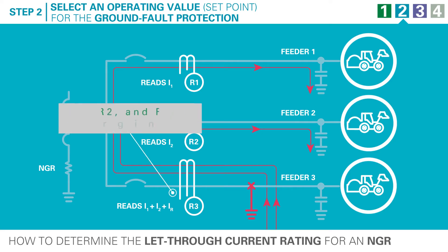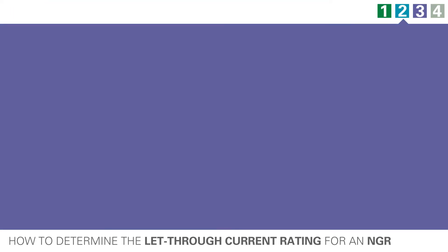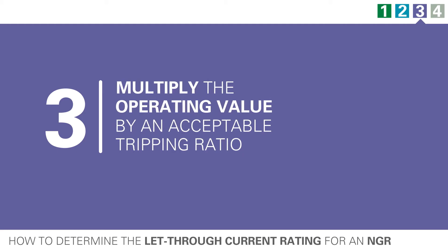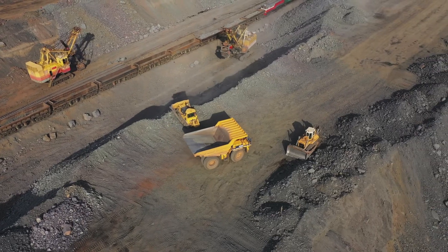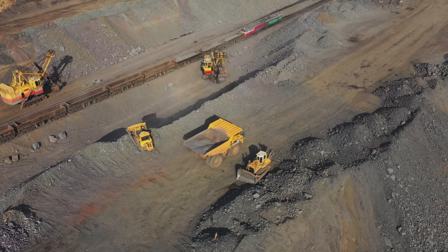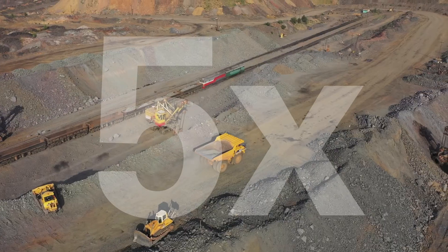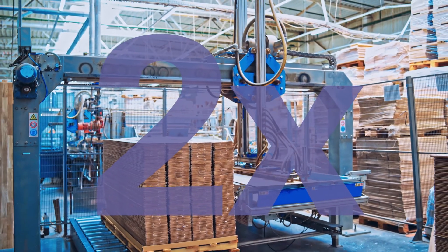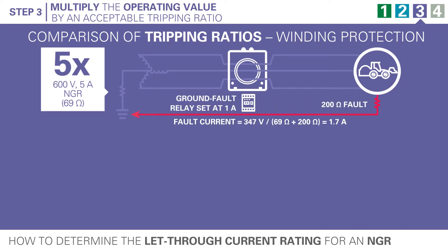In a properly coordinated system, only the faulted feeder relay will pick up or detect the ground fault. In step three, take that operating value and multiply it by the acceptable tripping ratio. Tripping ratio is the ratio of prospective ground fault current defined by the NGR to the operating value of the ground fault protection. The tripping ratio is also determined by the application: in mining applications where portable equipment endures harsh environments, a tripping ratio of five is common, while in an industrial application where the protection may be alarming, a tripping ratio of two could be used. An adequate tripping ratio ensures that sufficient ground fault current is available for detection when a ground fault occurs.